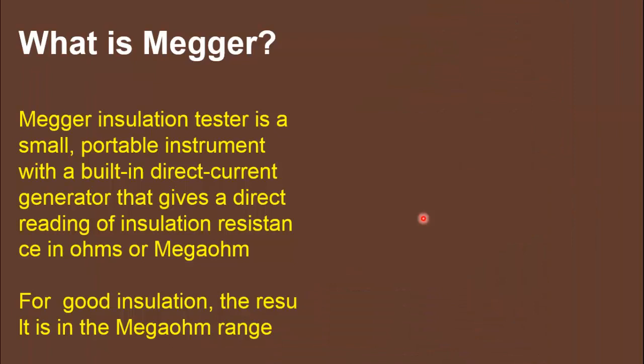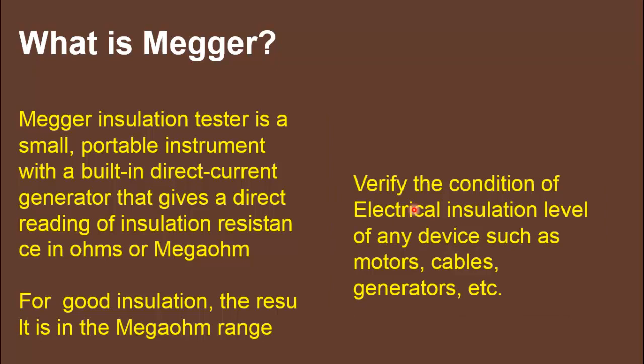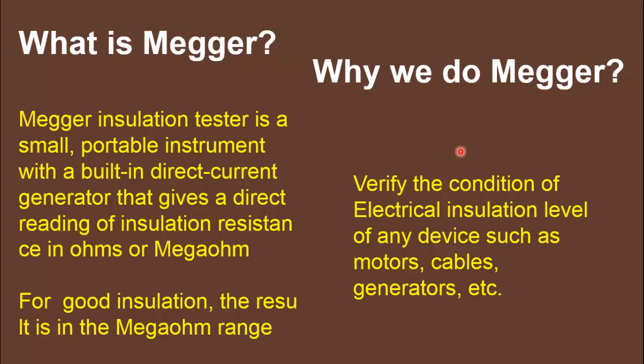First, I will explain what a Megger test is and why we perform it. The Megger test is performed by an instrument called the Megger insulation tester — a small device with a built-in DC generator that provides DC voltage to the equipment. It measures the leakage current internally and, using Ohm's law, displays the resistance value, allowing you to assess the insulation level. We perform the Megger test to verify the condition of electrical insulation on different machines or cables such as motors and generators.